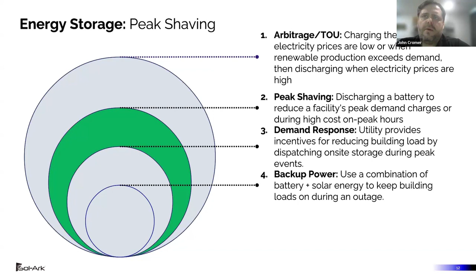Essentially, you want to look at your electric bill and see what percentage is a demand charge versus an energy charge. Even if you don't know the load profile of the building, a very high demand charge and very low energy charge typically means it's a good site for demand management, so you should proceed. If the demand bill is only 20 or 30% of the electric bill, you don't really have spiky peaks, you have a steady load throughout the day. So just by looking at the electric bill, you can get a sense of whether it's going to be a good project.